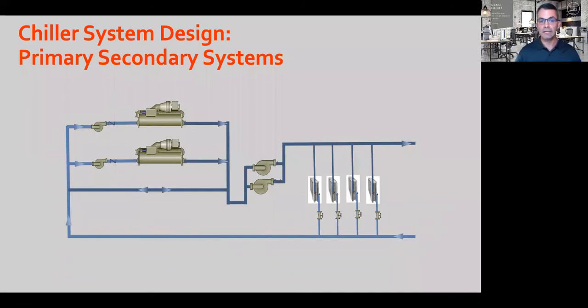Depending on how much flow you need out to the building load, the more 42 or 45 degree water that gets pulled into that loop, the excess is pulled through the bypass so that you are not wasting any energy. This is about 3 to 5% less efficient than a properly controlled variable primary system, and it uses more pumps. This is the old standby configuration, and sometimes you might have the thought of, if it's not broke, don't fix it. If you have it and it works great, it's easier to control. We might consider going to the variable primary configuration if you're designing a new plant.